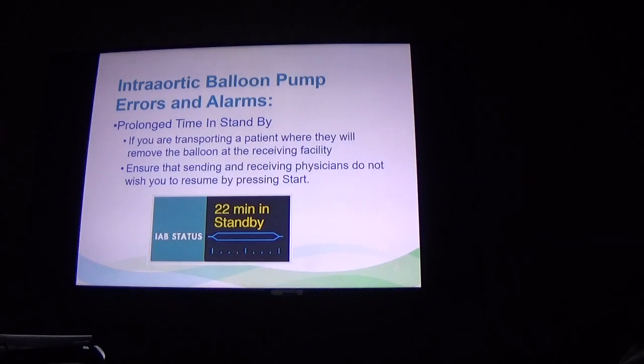So if for some reason, maybe you saw blood in the line and you had to stop it during a code, and you're running a code for 22 minutes, well, if you're doing compressions, it might give you this alarm, prolonged time in standby. It may be a point where you don't want to restart the device. Just ignore it, it's okay. Just don't hit start, because if you hit start, it's going to restart the device.